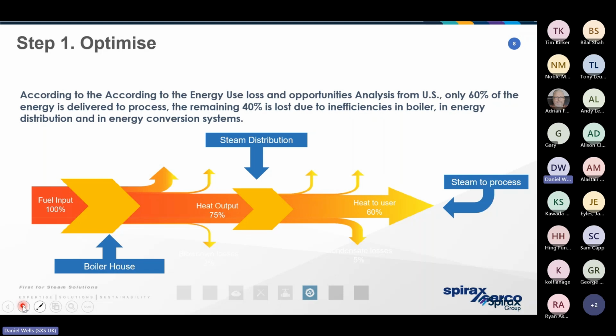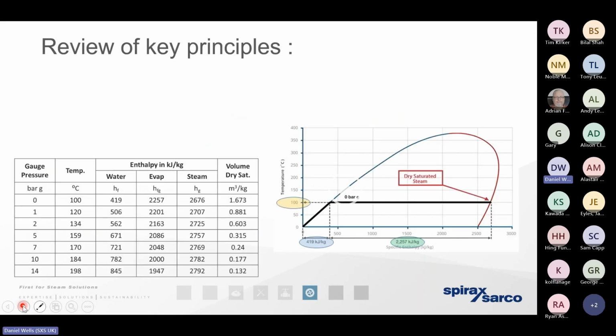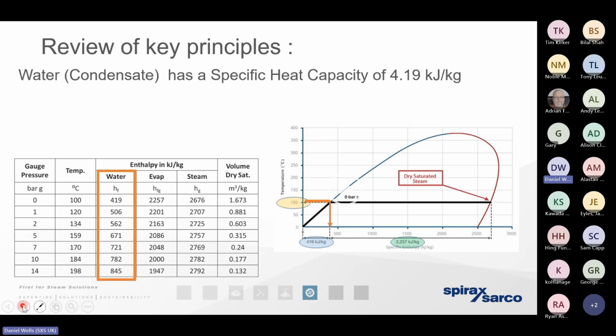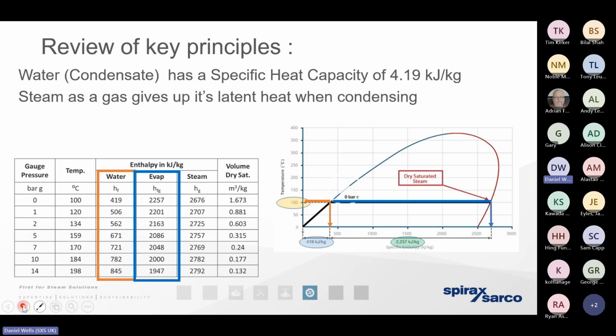even before we want to discuss or consider moving forward to apply those new technologies. So I've gone through the steam tables in some considerable detail in my previous presentations. I did warn you some weeks ago that I would go through this one slide in some detail on numerous occasions. So apologies for that. But what we need to remember is the steam tables, as fantastic a resource as they are, they only apply when the steam is 100% dry. And as we've mentioned in previous presentations, the drier the steam, the more energy there is contained within it. So if there's more energy contained within dry steam, the boiler doesn't have to work as hard, we're not producing as much gas, and of course, those carbon emissions are going to be kept to a minimum.